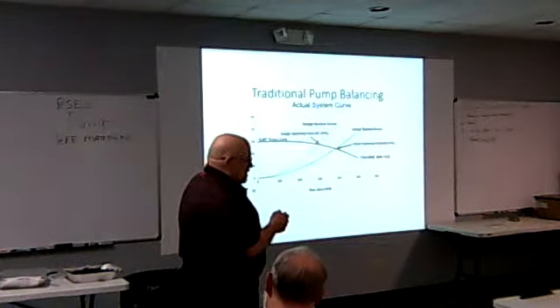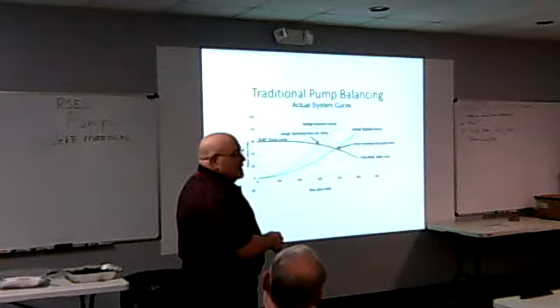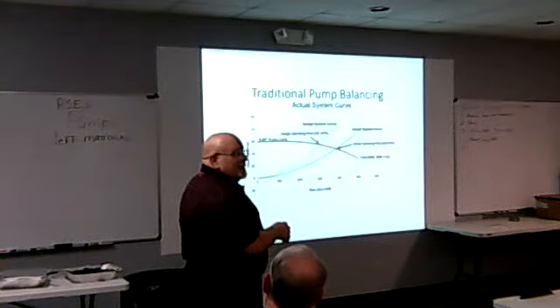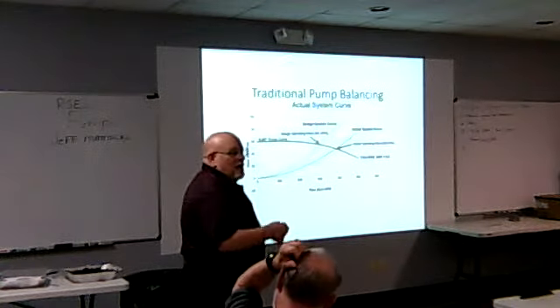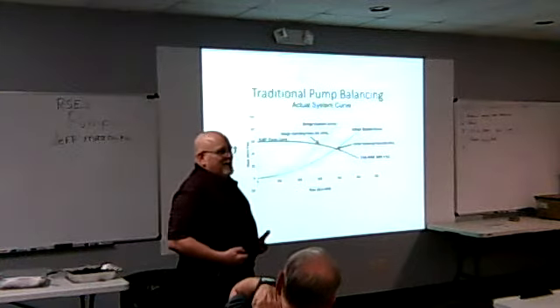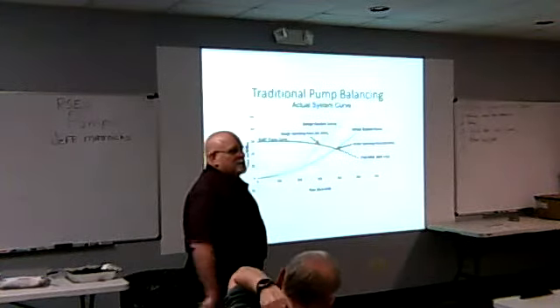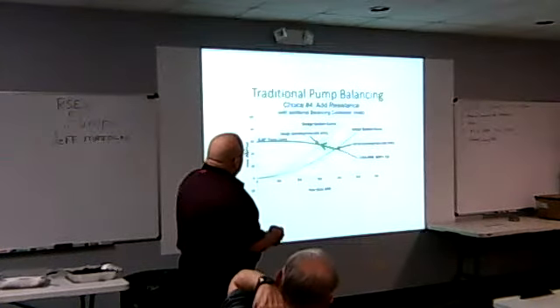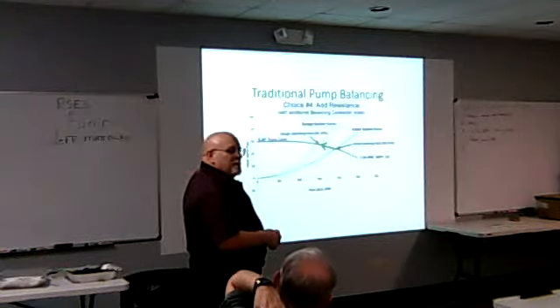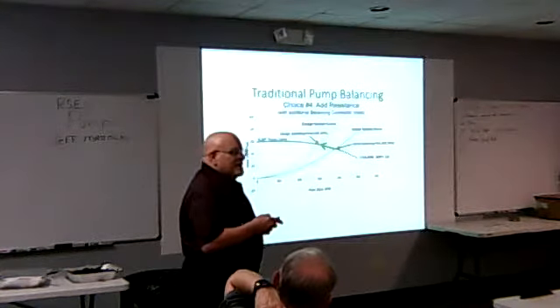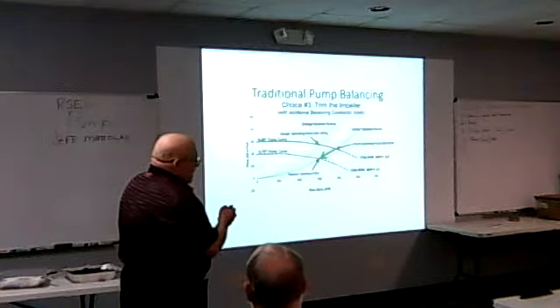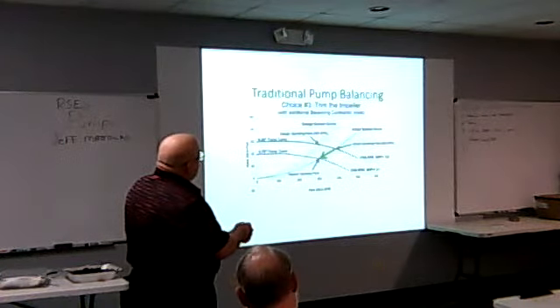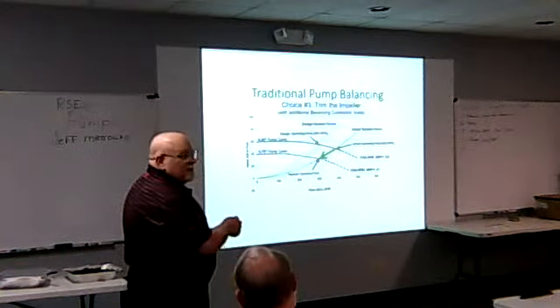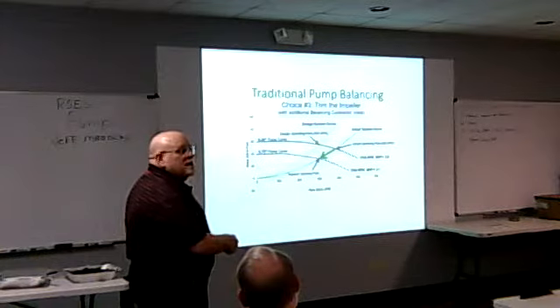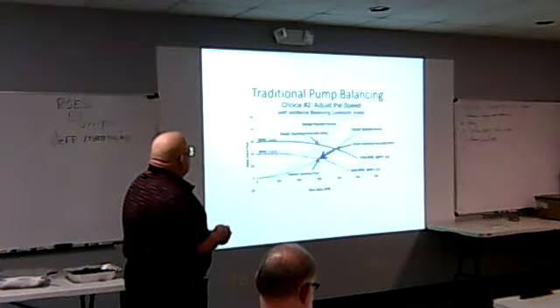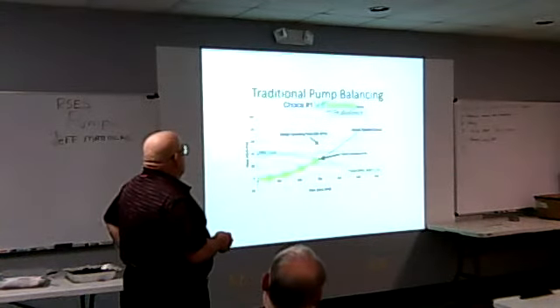In the old days, to make this correction, remember when I talked about what I do? Throttle the valve. What am I doing by doing that? Adding head. Now I'm turning more speed, I'm throttling off that valve, dropping that head, I'm paying money for something. You're just wasting energy on the motor. Whereas the self-sensing is going to shift its curve back up where it wants to be. It slows down, you're saving the energy, and puts you on the spot. And the way they work is, as the system flow changes up and down the system curve, the pump will actually step down. It'll step curve to curve to curve to curve till it gets where it knows it needs to be. Pretty neat concept. And it's getting more and more popular.